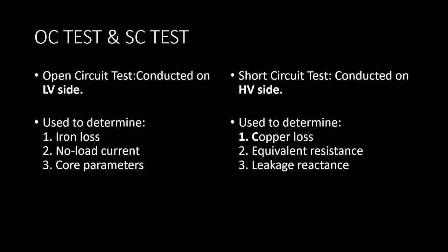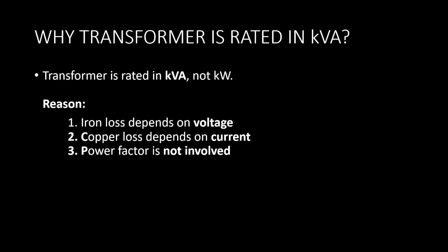And the short circuit test is conducted on the high voltage side and used to determine the copper loss, equivalent resistance, leakage reactance and all these things. Basically, the power input during the short circuit test is very small. It can be an important point for you.